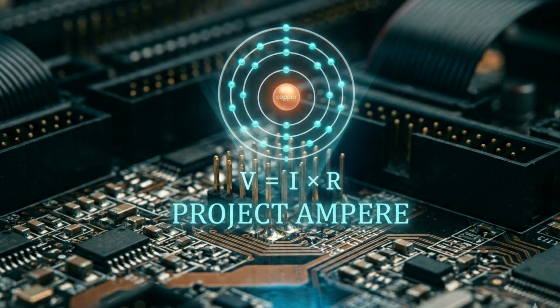The fuse element instantly vaporizes into plasma before it even has time to glow red. If you witness that exact violent signature, your absolute worst move as a technician is to install a larger amperage fuse just to see if it holds. Because if you do that, you bypass the engineered weak point.